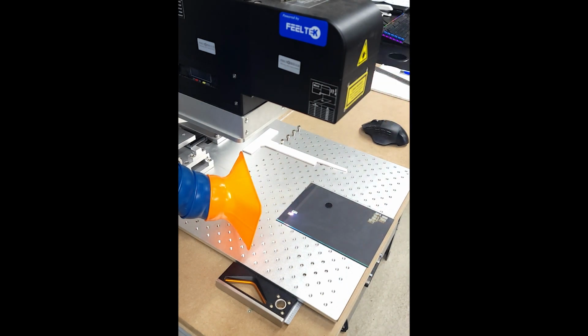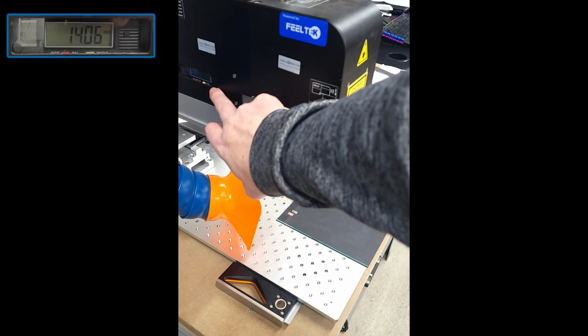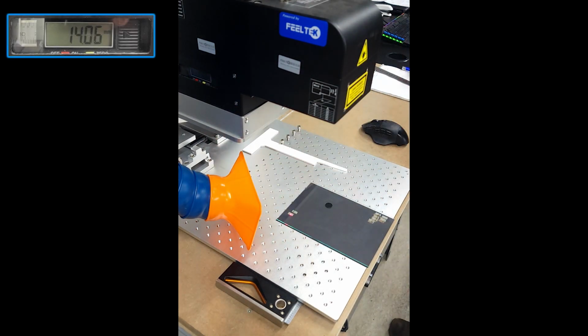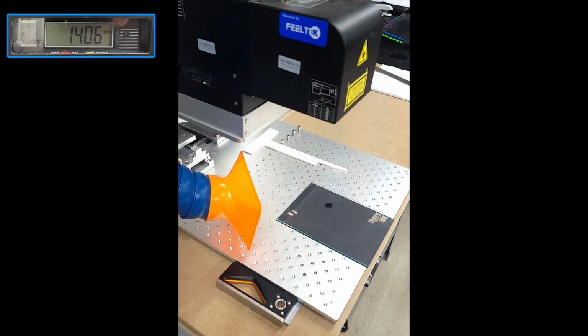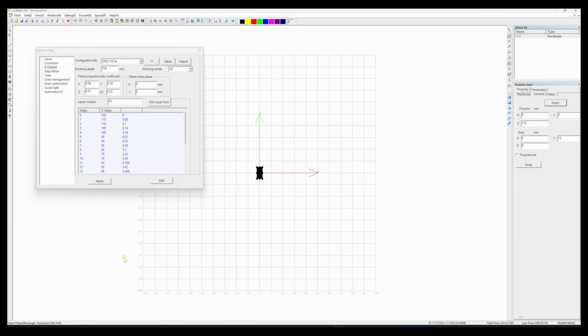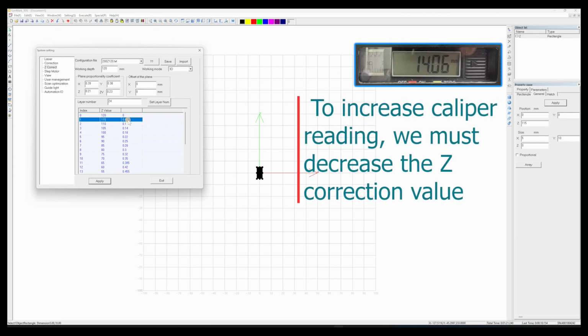That looks like it right there. Now again, we're going to reference our caliper value. So we're at 14.06. What we need to do is adjust our Z calibration value until we get that strong beam at 14.15 again. Now I mentioned that the reading from that was 14.05. We need that value on the caliper to go up. Now to do that, we're going to lower our Z value. Let's try 0.04.